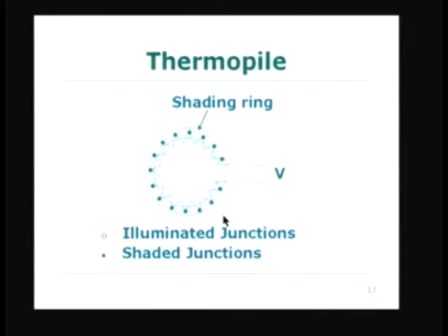In fact, we have also indicated here another use for thermometry. If you remember, we were talking about measurement of temperature, and suddenly we have shifted our emphasis. Here I am talking about measurement of solar energy. So, actually the heat flux from the sun can be directly converted to the increase in the temperature of the junction, and this is proportional to the amount of heat falling on it, and therefore, I am able to measure the solar flux using essentially a thermocouple or a thermopile in this case. It is called a thermopile because a large number of thermocouples are in series.